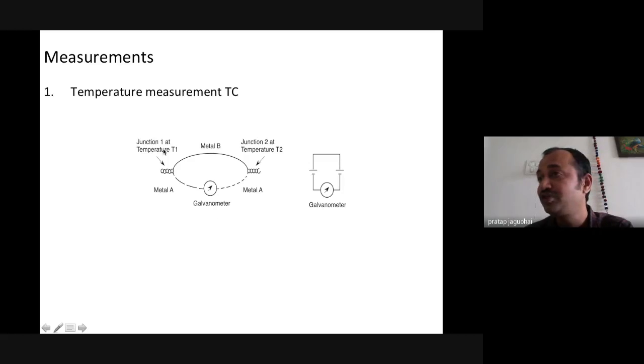Another important temperature element for higher temperature measurement is the thermocouple. The thermocouple is governed by the Seebeck effect, where two dissimilar metals are welded or joined together, and if one of the ends is heated, you can get an EMF, which can be measured in the form of voltage in millivolts. We can signal condition it and define the voltage output, which is proportional to the temperature.